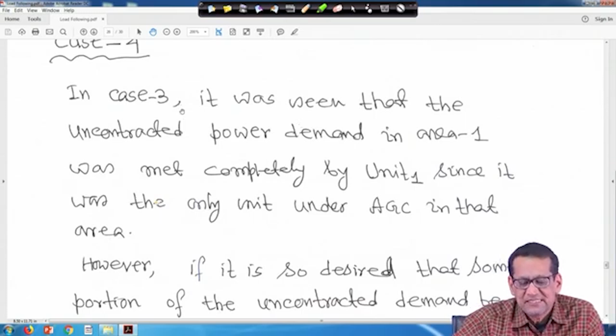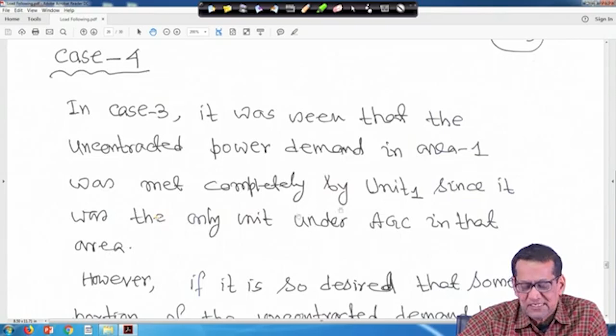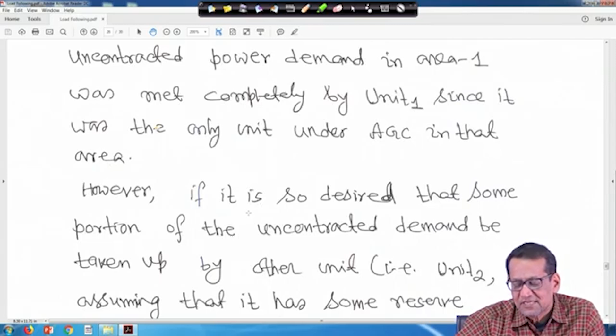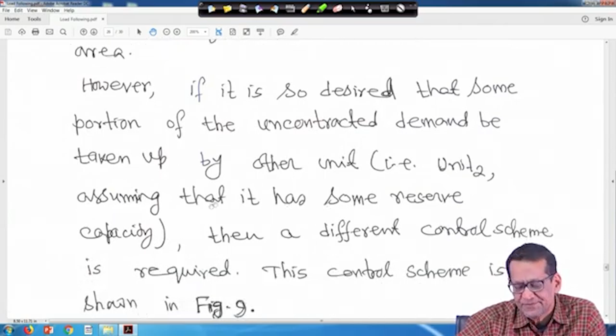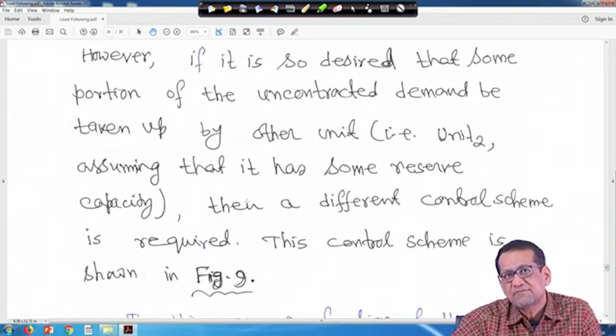So, next one is case 4. In case 3, it was seen that the uncontracted power demand in area 1 was met completely by unit 1, since it was the only unit under AGC in that area. However, if it is so desired that some portion of the uncontracted demand be taken up by another unit, that is unit 2 in area 1, assuming that it has some reserve capacity, that is spinning reserve, then a different control scheme is required. This control scheme is shown in figure 9. I will show you figure 9.